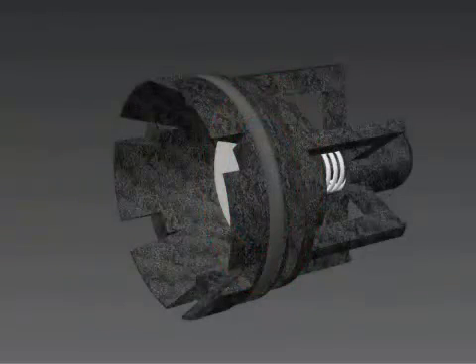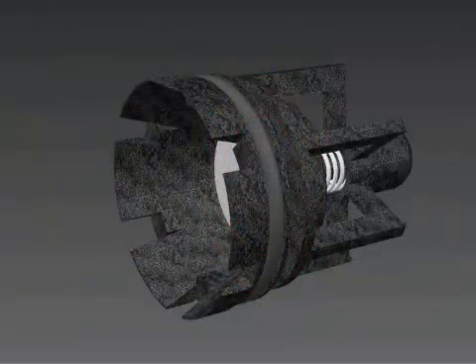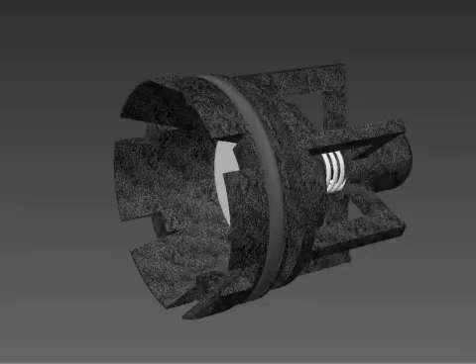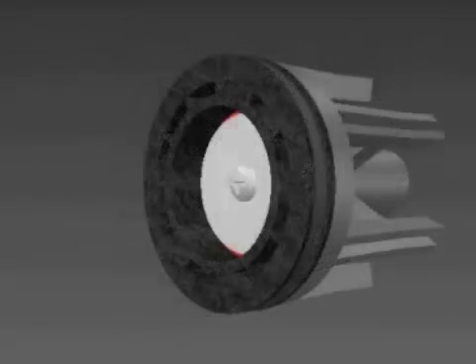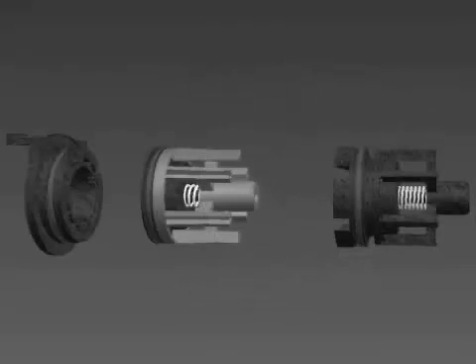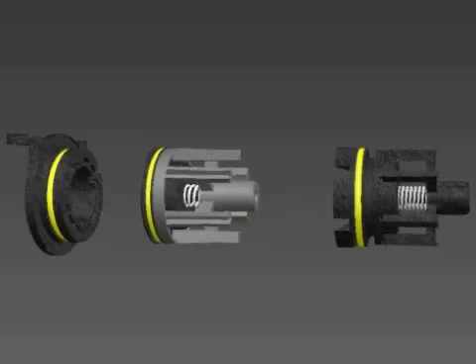Repeat this process with the second check assembly. Make sure to put the stronger spring in the number one check assembly. Now place your new O-rings on the seats of each check assembly and the sleeve if needed, and lubricate these O-rings.